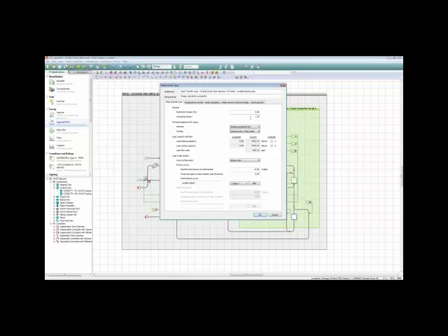You have a number of options about, for example, the principal equipment for sizing. This is the new concept in Apache HVAC, where you can nominate something to be sized sufficient to cover the entire load, and then you have other things which are sized at some fraction of that, so that those items can, for example, be first in line to try to address the load, and then ultimately whatever this item is is your backstop to make sure you do have enough capacity to address your auto-sized loads if you choose to go that route.